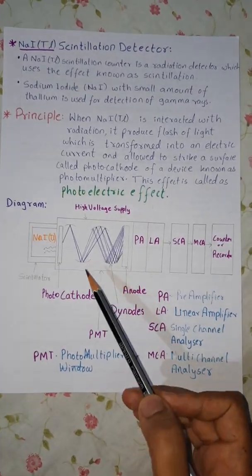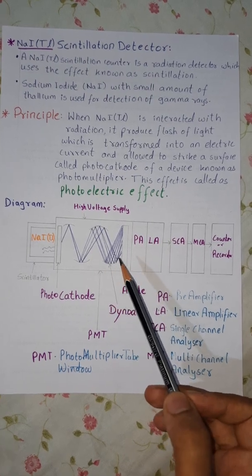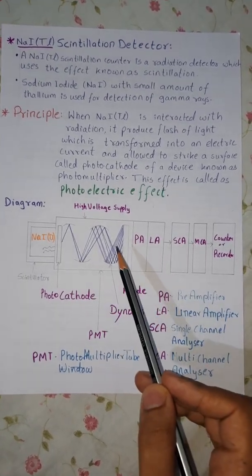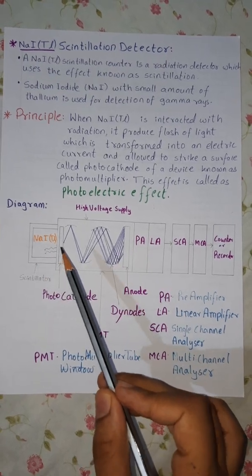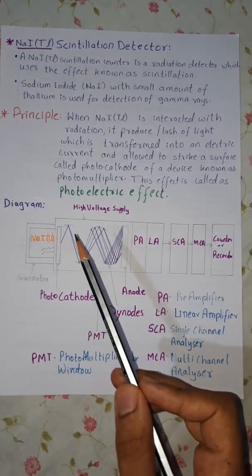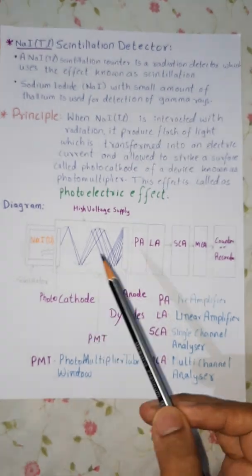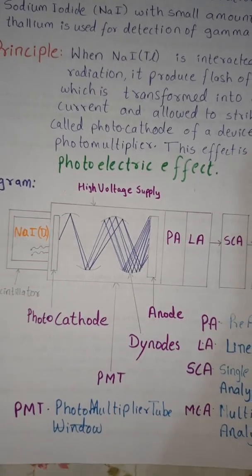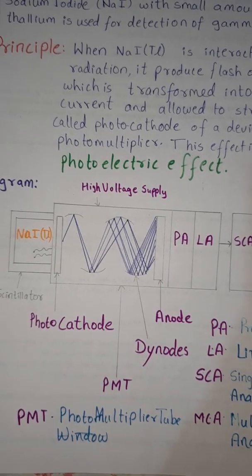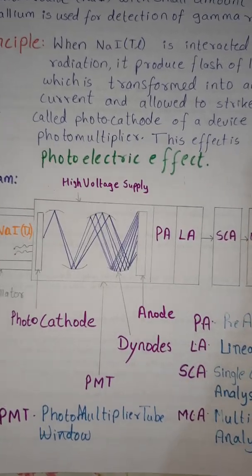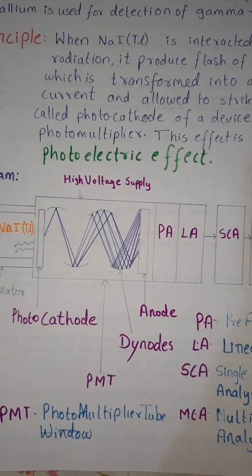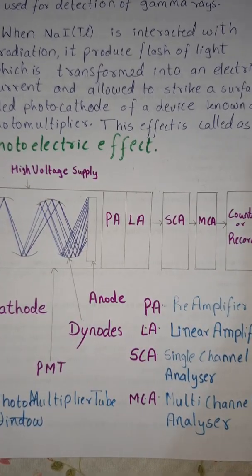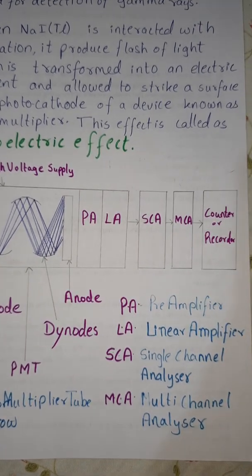This is then transferred to the PMT that is photomultiplier tube. Here there are various dynodes. These excited electrons multiply at subsequent level in the dynode as they have very high potential level at every stage. From here they are connected at the anode and from anode they are sent to the PA and LA which is pre-amplifier and linear amplifier.